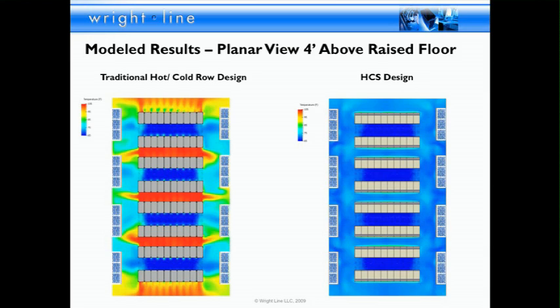But here is a working data center. This is a working data center in a traditional hot aisle, cold aisle. It's got 8 CRAC units along the aisle. You're looking at a plan view, and I'm taking almost like an MRI slice, 4 feet off the ground. What does that look like? This is an operating data center. This is all open. There's no containment, open air. As you can see, the hot aisles, go figure, they're hot. The cold aisles are cold. This is with all 8 CRAC units running.